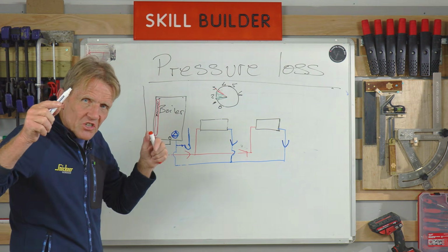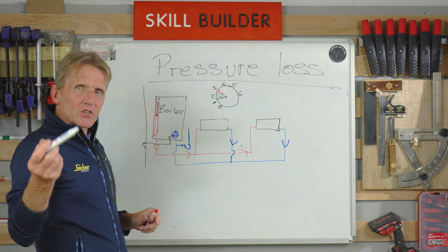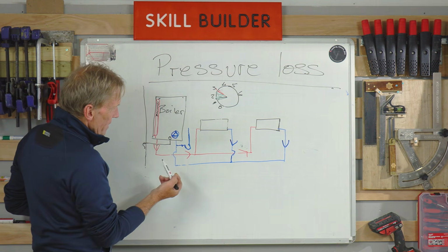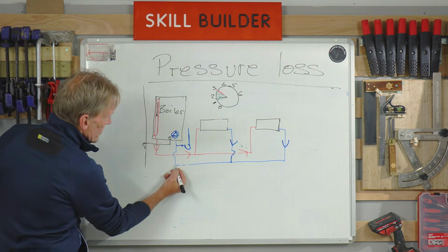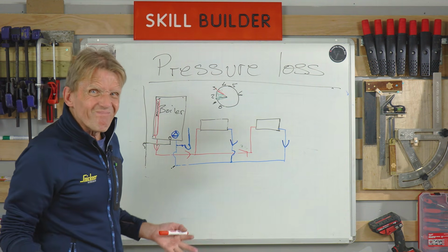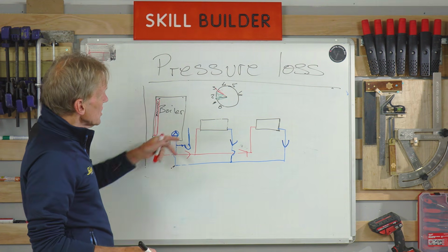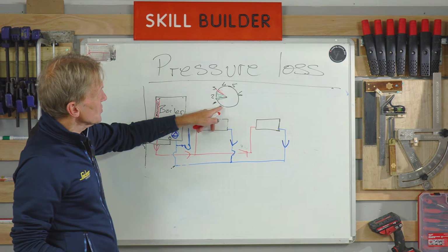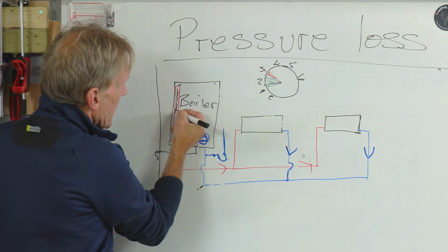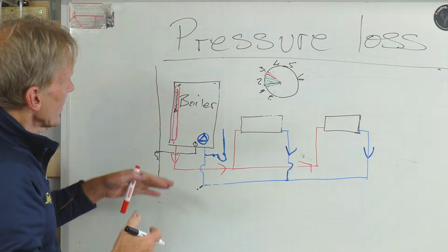Now, it's important when this is done, by the way, if you're topping up the pressure on your expansion vessel, you need to relieve the water on the system somehow. If you've got a drain cock on the system, you need to drain a little bit of water out. You don't have to go crazy, you can put less than half a bucket or something like that of water out of the system, just so that that pressure gauge drops to 0, and then you can pump up that vessel there, and so long as that hasn't gone up, you're still fine. You're not pressuring it against the water.